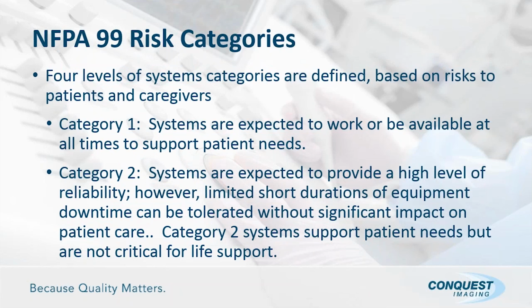There are 4 levels of risk categories associated with NFPA 99, for the different systems. Category 1, the systems are expected to work or be available at all times to support patient needs. This is the highest level, the most critical category as far as risk categories go. Category 2, systems are expected to provide a high level of reliability. However, limited short durations of equipment downtime can be tolerated without significant impact on patient care. Category 2 systems support patient needs but are not critical for life support. And so that's really the key point between category 1 and 2, that they're not critical for life support. However, they still play a very important role as far as patient needs go.